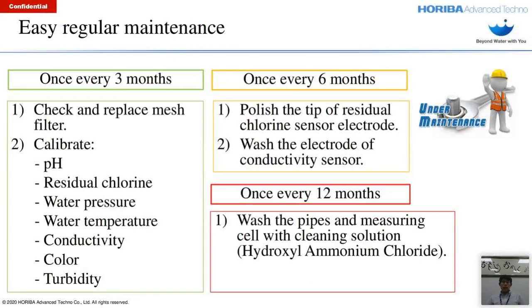Okay, next I'd like to talk about maintenance. Depending on the maintenance cycle, different maintenance procedure has to be conducted. As a rule of thumb, calibration of sensor and visual inspection of filter has to be done once every 3 months, and cleaning of sensor has to be done once every 6 months. Last but not least, cleaning of pipes and measuring cell has to be done once every 12 months using hydroxyammonium chloride, which has to be prepared by the user locally.